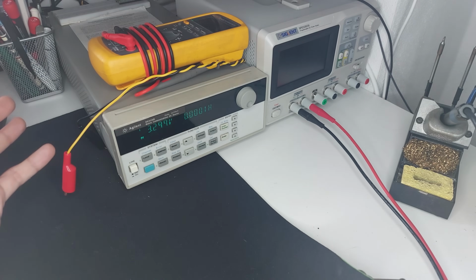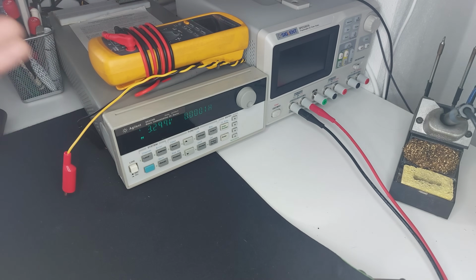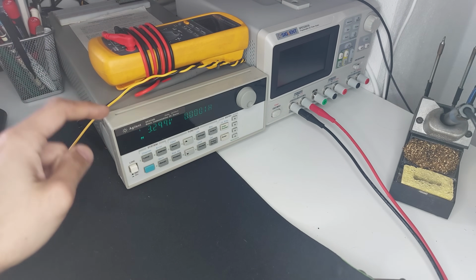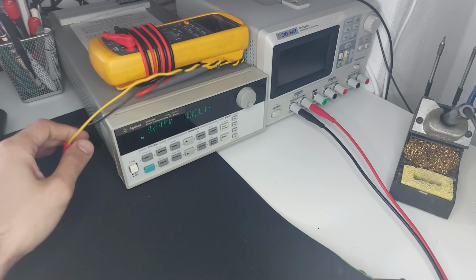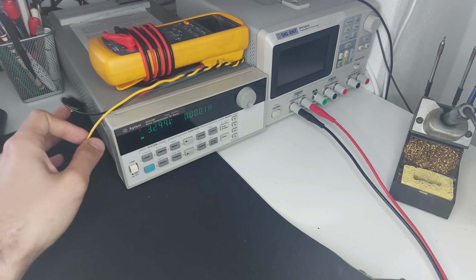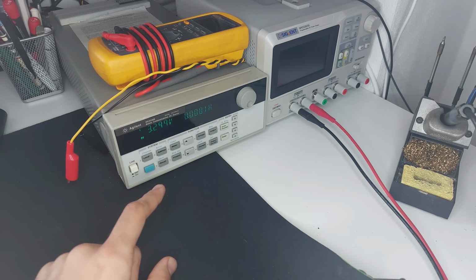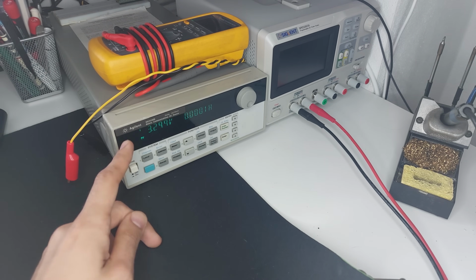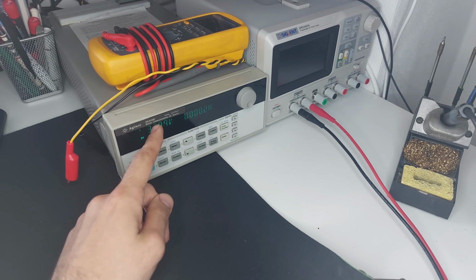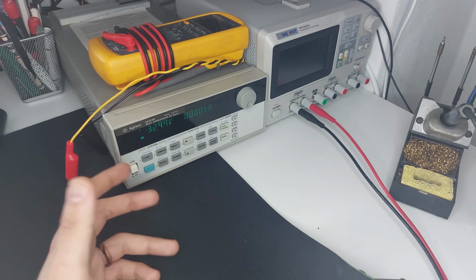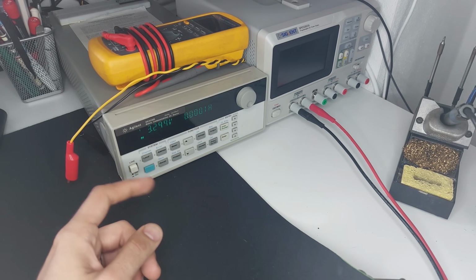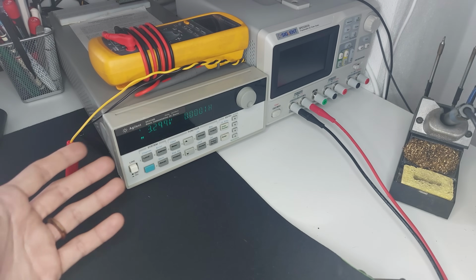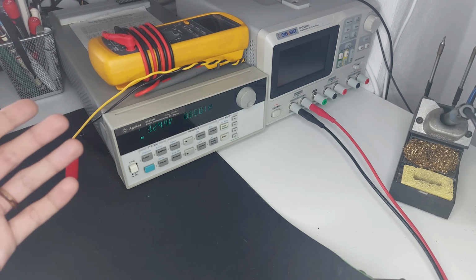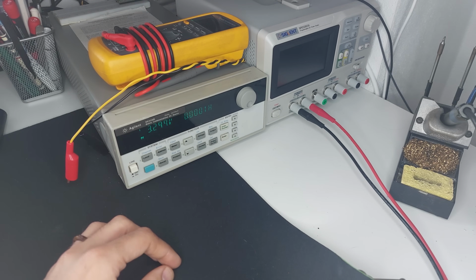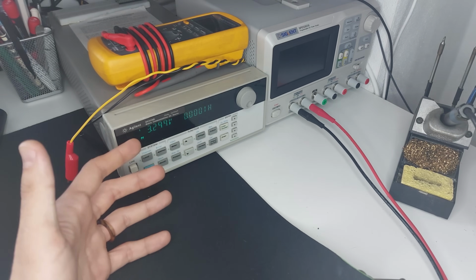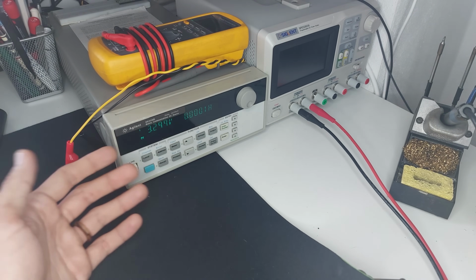So it's built like a tank. It's got a massive transformer. It's got a load dependent fan, but you're going to see that it's quite loud. Even when it's not drawing any current, it's quite loud. Another disadvantage of this kind of power supply, because it's a system power supply, a mobile communications DC source, so it's not a lab power supply theoretically, is that it's meant to hang around in the back of a rack in a giant piece of industrial equipment on the assembly line or something like that, or on a long-term test bed.